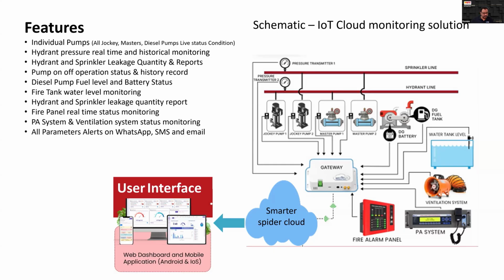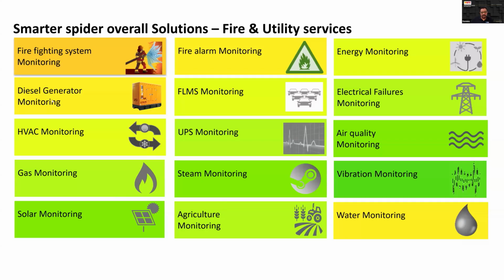Then we have the fire tank. In many situations, even in the most expensive apartments which I've seen, they don't maintain enough water for firefighting. Whenever the water level is down, you can get an alert that there's no water in the sump, the overhead, or the storage for firefighting. You can also monitor the fire panel, that is, the fire detection panel. Whenever it goes into alarm condition or fault, you get an alert. Your PA system, ventilation system, and smoke management system can be monitored. All of this can be monitored through a simple app-based software or dashboard, which can give you alerts. Not only that, this particular app can monitor diesel generators, HVAC, gas monitoring, and all that.